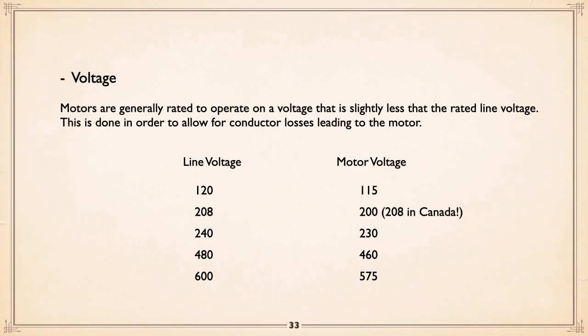Voltage. Motors are generally designed to operate on a voltage slightly less than the rated line voltage. This is done on the assumption that you're losing power through conductors before you actually get at the motor. For example, line voltage 120, the motor will typically be rated 115. 208, the motor will be rated 200 in the States. In Canada, they rate them at that voltage, and I guess they assume the power transformers will be close. I don't know why we do it. Canada, we're a little weird. Anyway, 240 volt is a 230 motor, 480 volt would be a 460 rated motor, and 600 volt would be a 575 rated motor. Now you know why the differences.